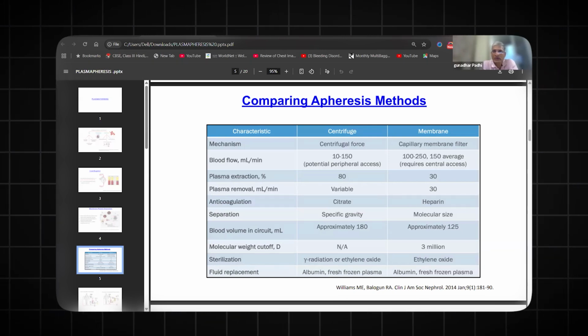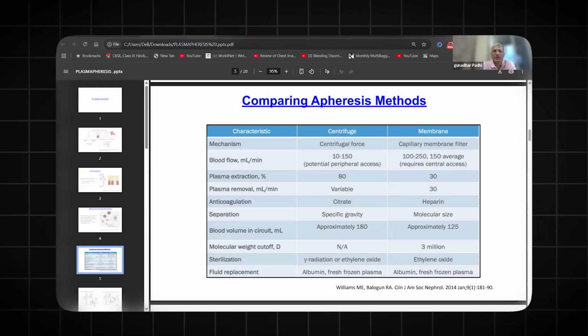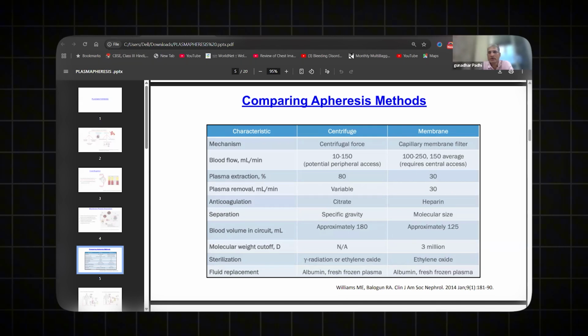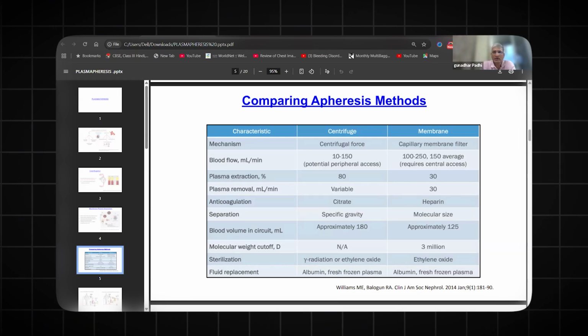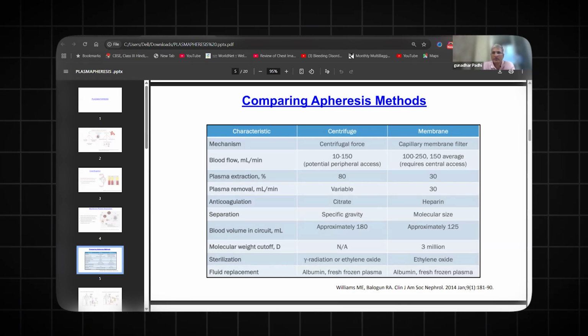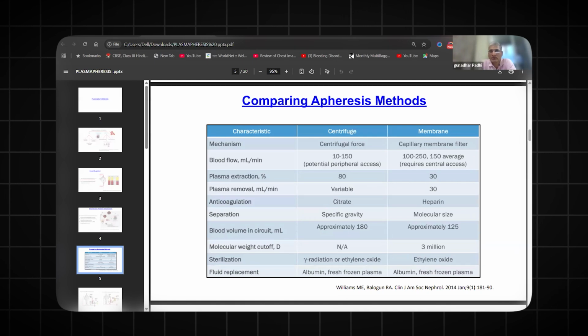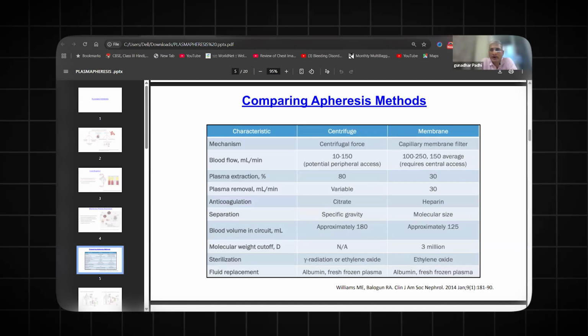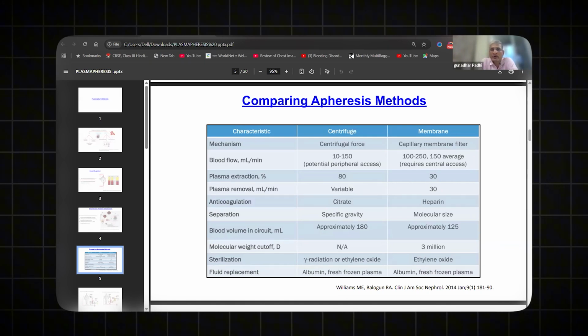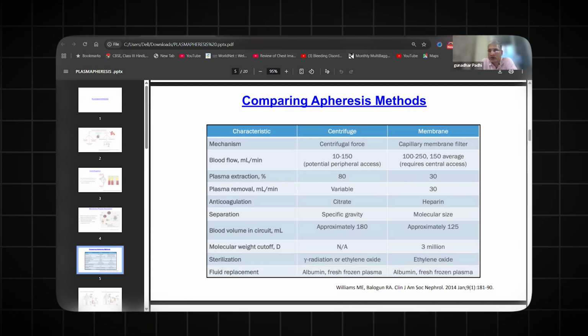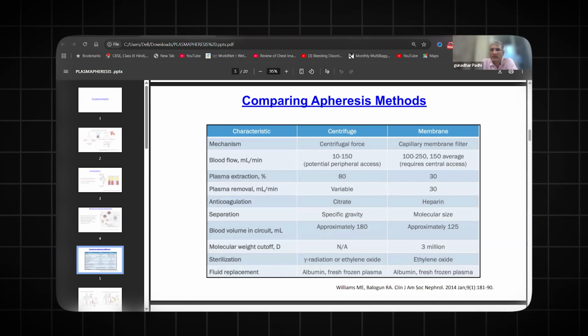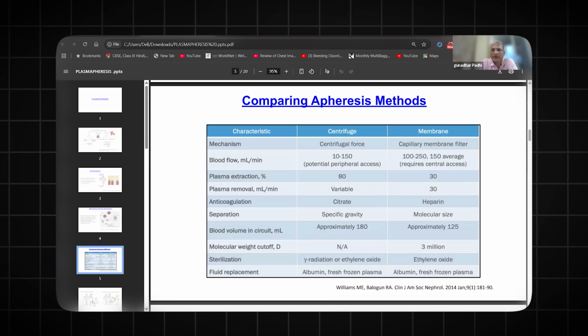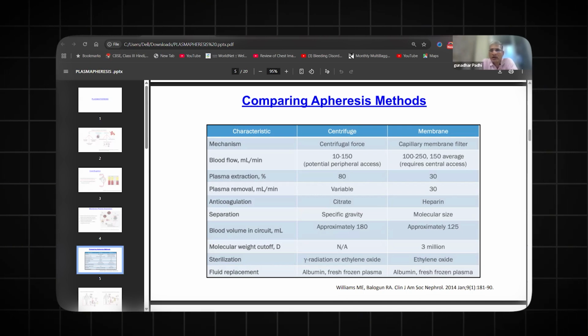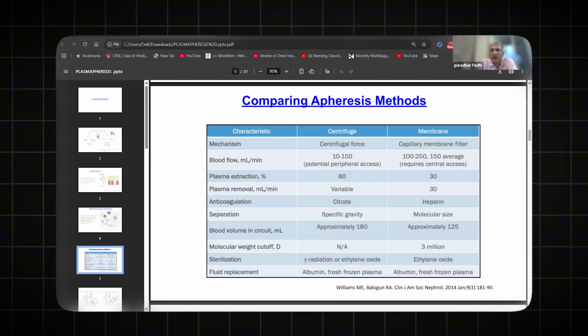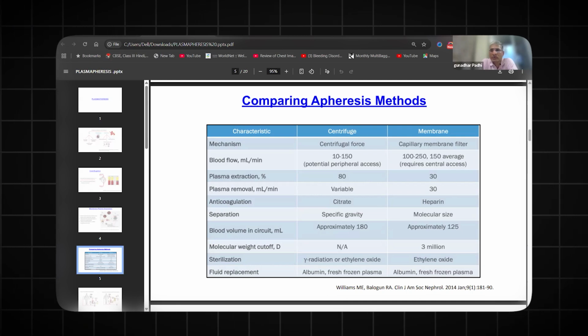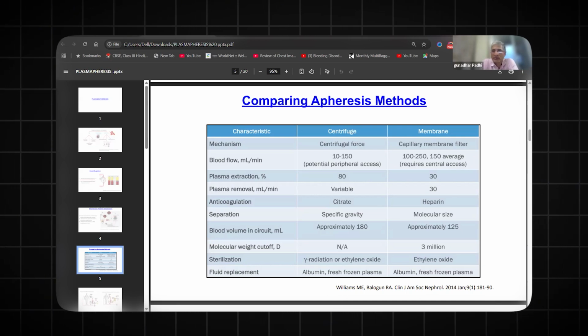And here the most important thing is that for the centrifugal technique you don't require a central line; you can do it through a peripheral line. You just connect the pump to the peripheral line, the pump will rotate and suck the blood, and the filtration can happen. Compared to your CRRT machine or normal dialysis machine, where you require a dialysis catheter. This is one of the very important differences, because you have to put in a dialysis catheter to carry out this procedure, like membrane plasmapheresis.